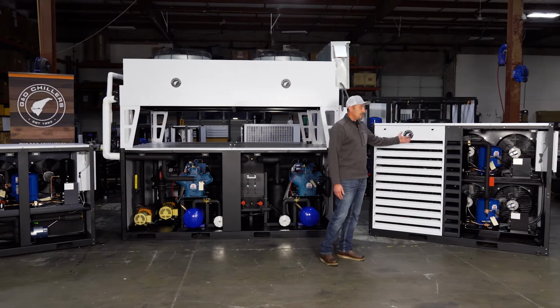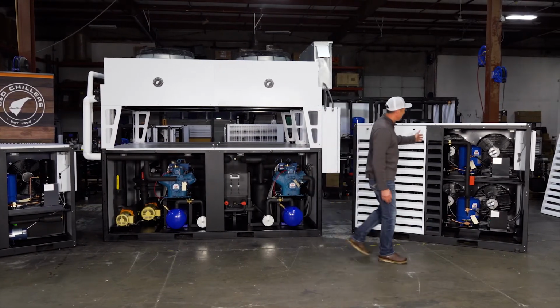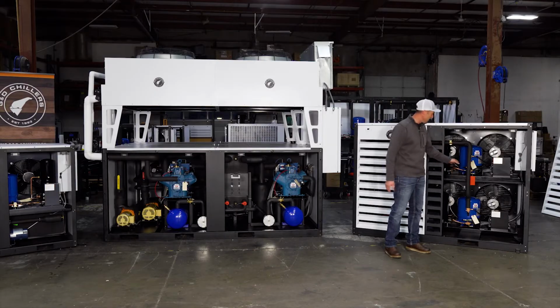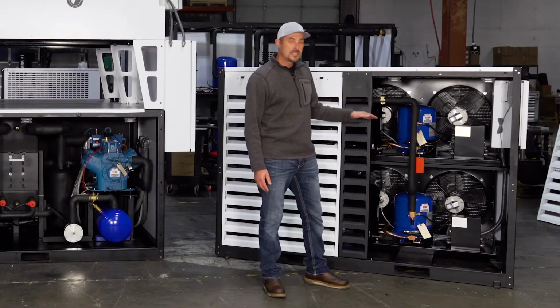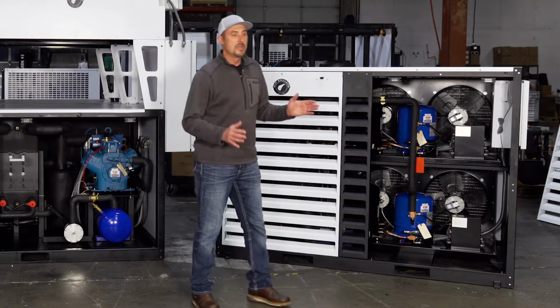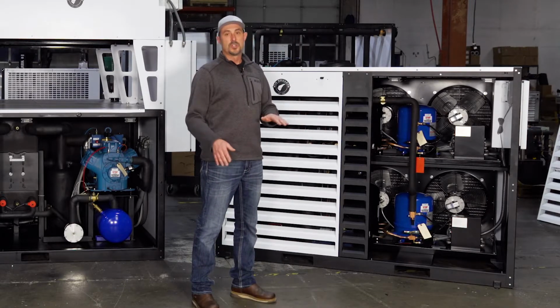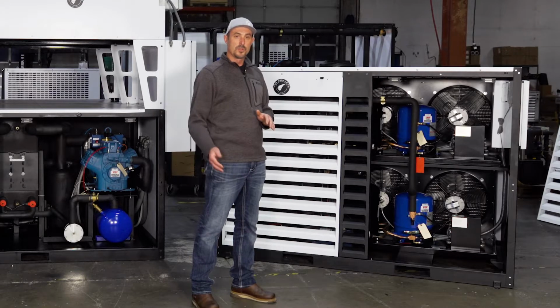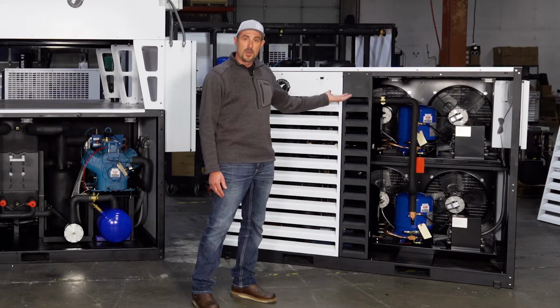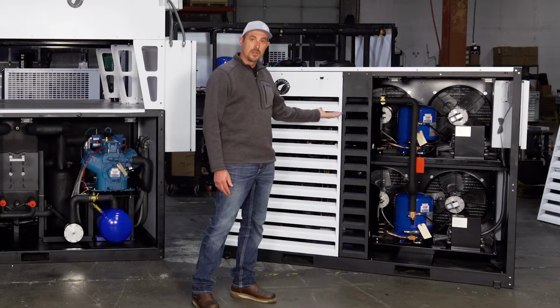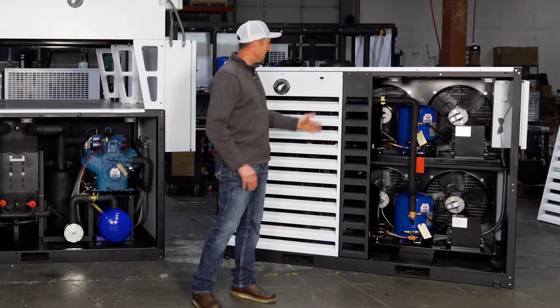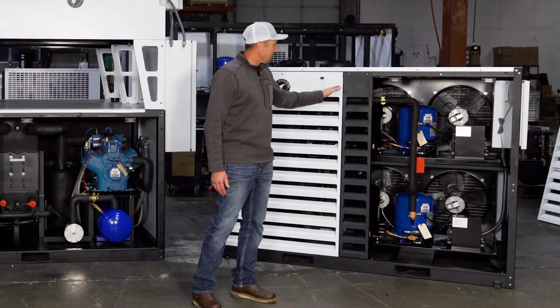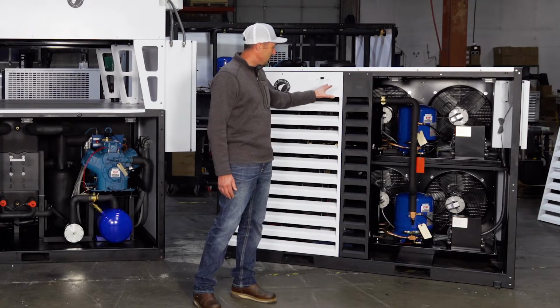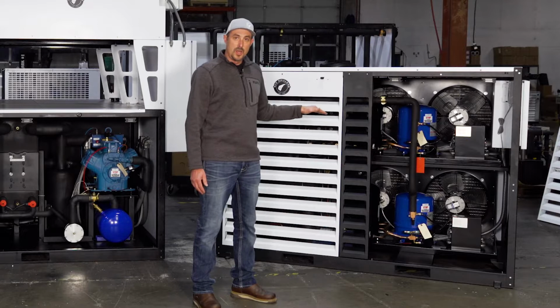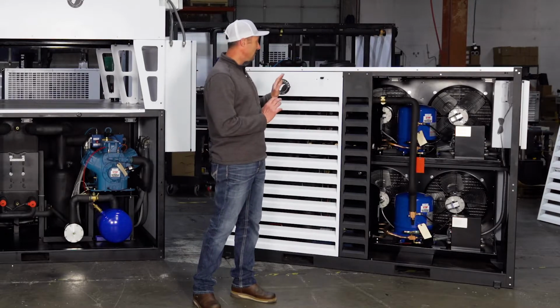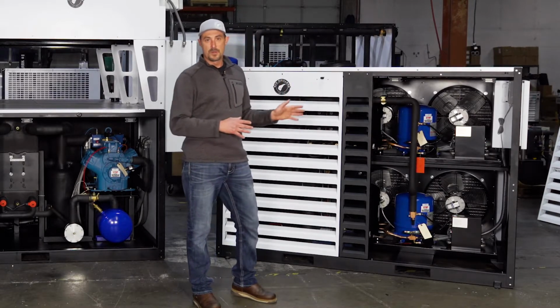Jumping to this unit, this is our dual stage chiller. It has two of the same compressors you see over there, which allows you to stage cooling as needed. In a brewery, your load is going to fluctuate up and down, especially if you're knocking out wort with your chiller. This allows one compressor to come on when needed, while the other cycles off - they alternate for equal runtime. The other benefit is if there's ever an issue with a fan motor or one refrigeration circuit, the other would still operate. That's unique to G&D, giving you 50% redundancy, which is very important in production facilities.